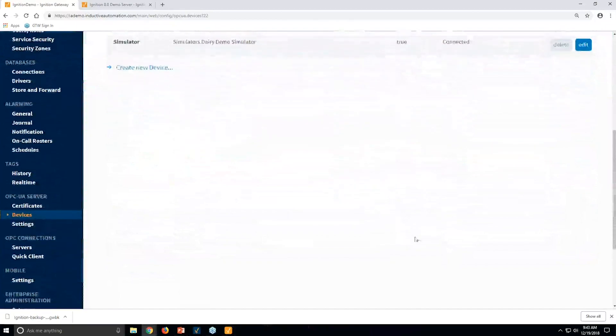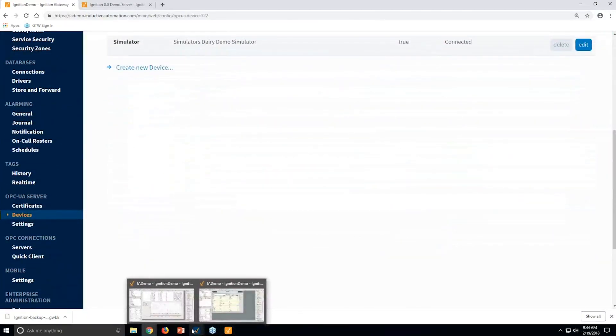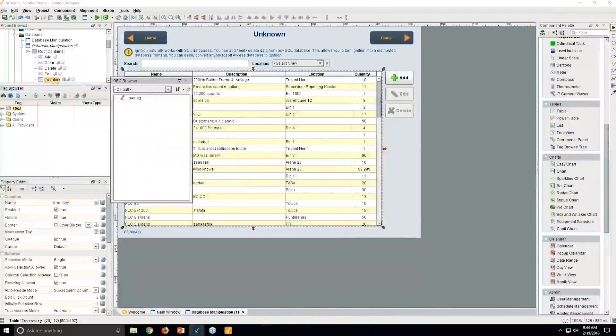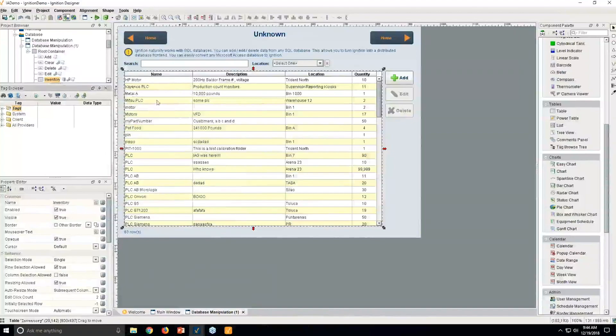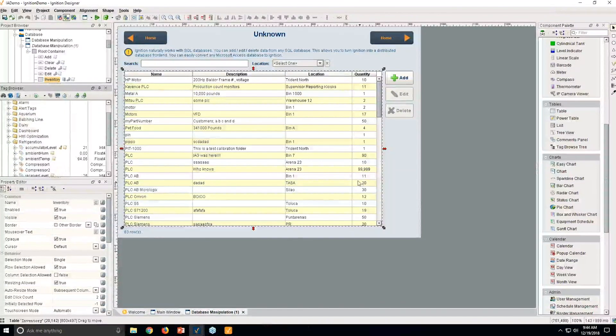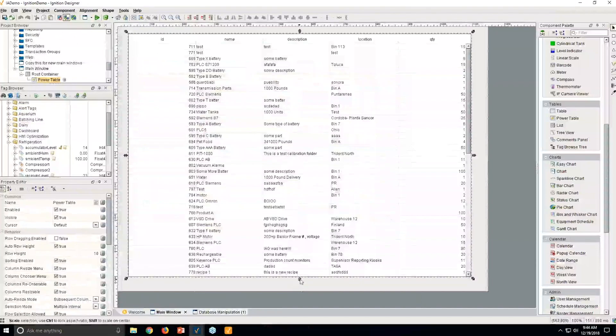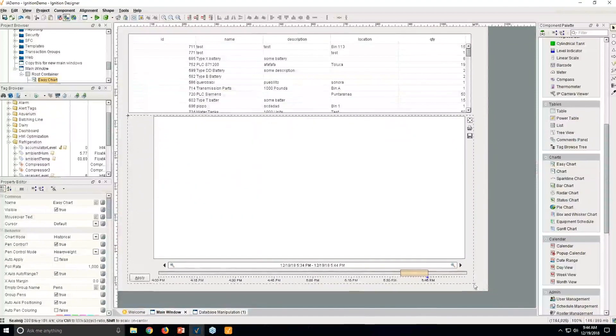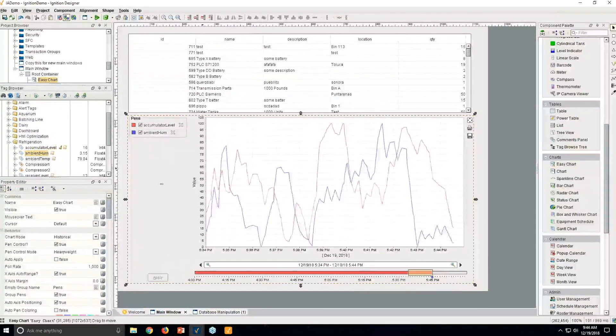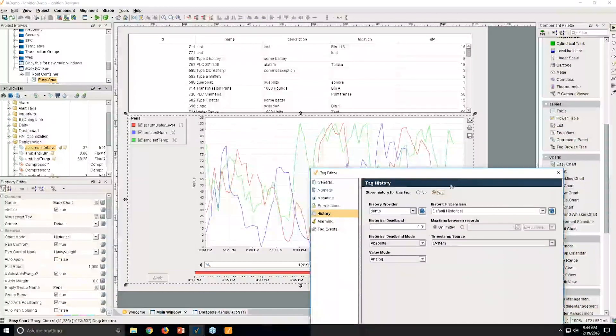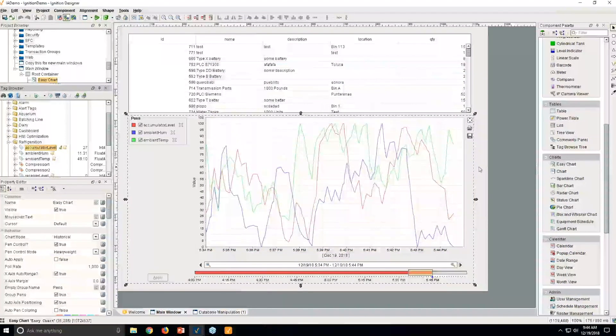We're connected to a couple of other things from this server. Switching over to the designer I just launched, you can see this device is now inside my configured devices. I can browse down to it and look at that device. If I want to pull these tags into the Ignition tag system, I can do that and use them in a variety of ways — for instance, alongside a table I created earlier. I can drag them in, and I can enable history by going to the history section and selecting yes. That's really all it takes to pull history in.